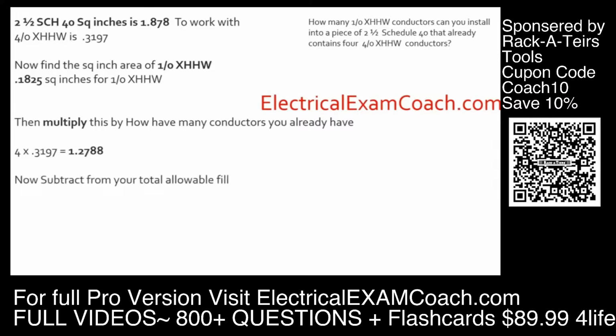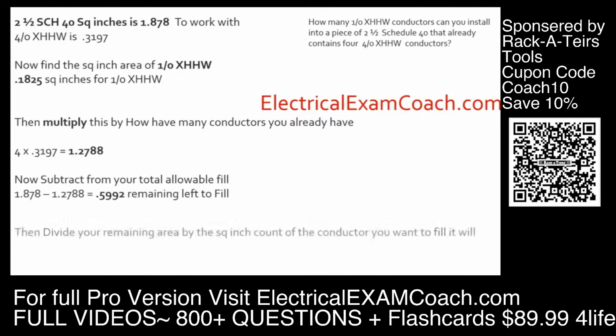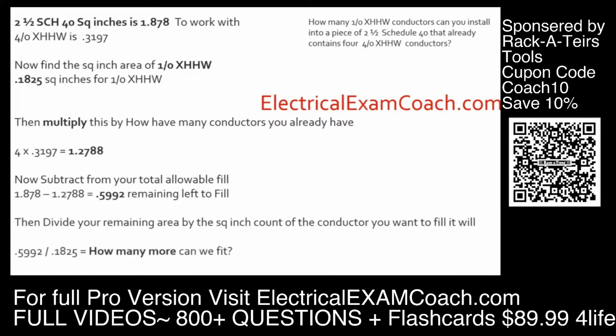Then what we're going to do is take our total area that we were able to fill and minus what we have, and that lets us know what we have remaining left to fill. Then all we have to do is divide. We take our remaining left to fill, divide by our individual 1-aught, and that lets us know that we can fit 3.28 conductors. We are below 0.8, so we're going to round down, and we find that we can fit 3 more in the conduit.